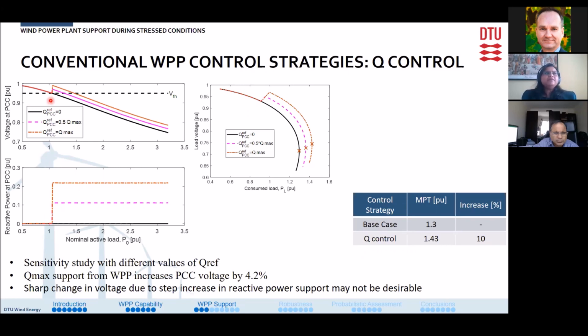And we can see here that if we provide maximum support when the grid is during stress voltage conditions, the PCC voltage increases as expected, but there is a sharp change in voltage due to the step change in reactive power support here. However, as seen in the PV curve here, if we provide maximum reactive power support during Q control, then the maximum power transfer capability of the system increases by 10% when compared to the base case.